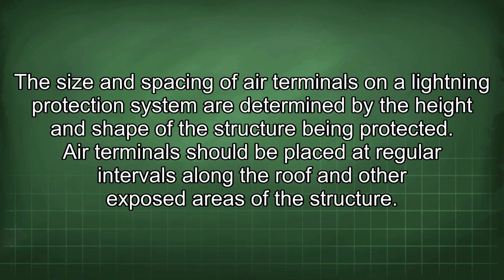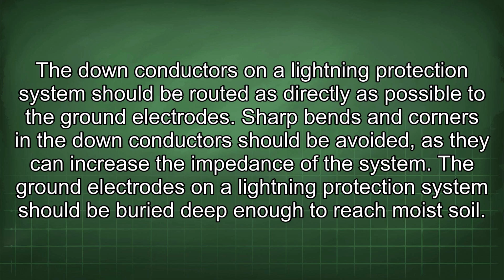Air terminals should be placed at regular intervals along the roof and other exposed areas of the structure. The down conductors on a lightning protection system should be routed as directly as possible to the ground electrodes. Sharp bends and corners in the down conductors should be avoided, as they can increase the impedance of the system. The ground electrodes on a lightning protection system should be buried deep enough to reach moist soil.